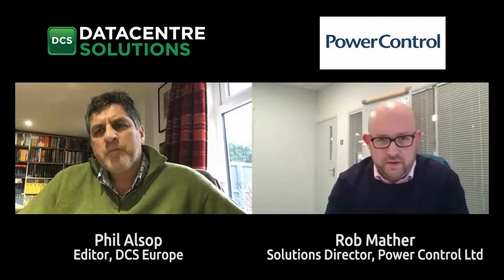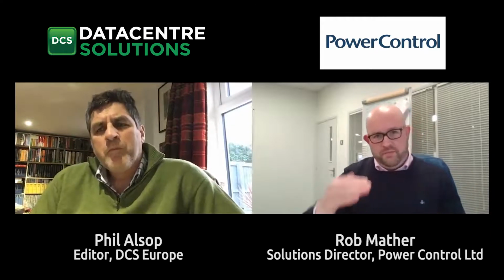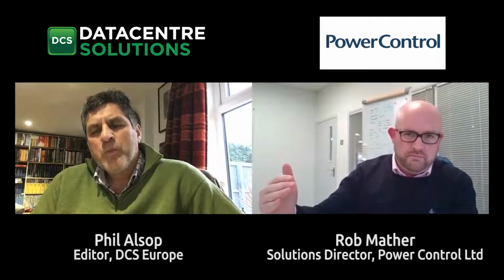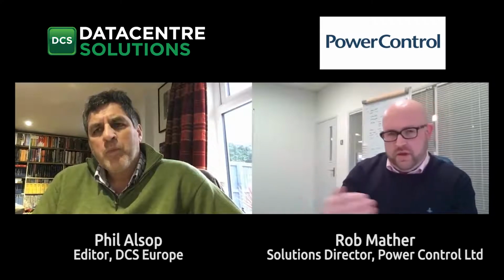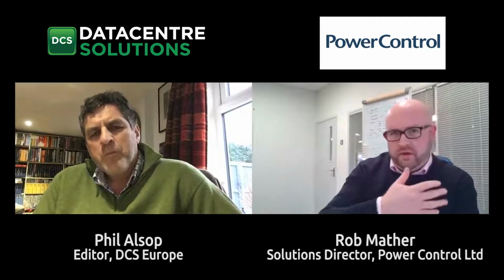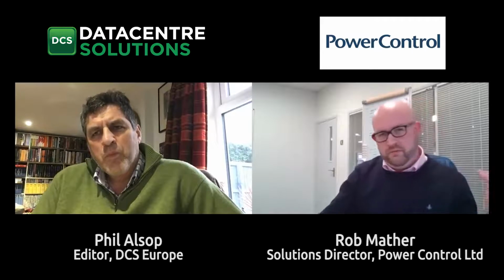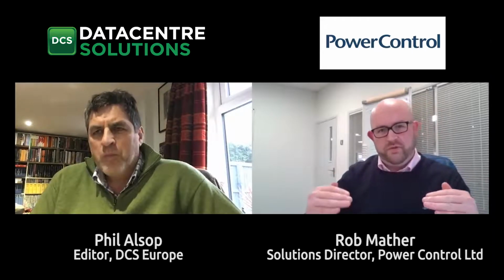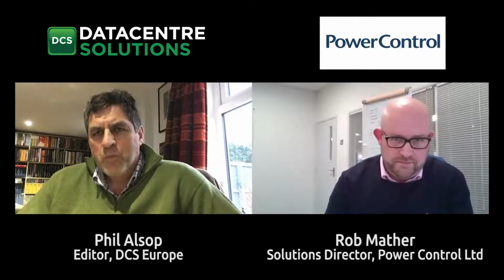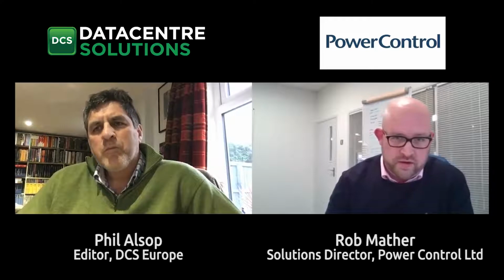It has the same effect. I'm not sure if you know what peak shaving is, but that's where you can cap the input to the UPS. So say it's a 2 megawatt system, and normally you'd have supply coming in for everything at that, or perhaps a little bit higher, but then that can be reduced down to a 1 megawatt input. The UPS will then load share between the mains and the battery, and it'll use the battery to top up what's missing for a short amount of time. Obviously, you do need to oversize the battery a little bit to do that, but personally, I think that's a better way of doing it rather than exporting back onto the grid.